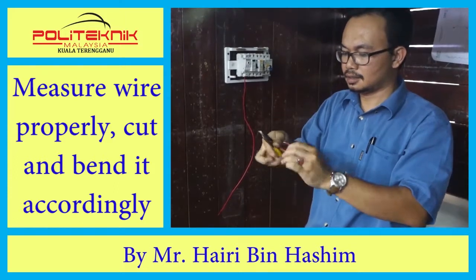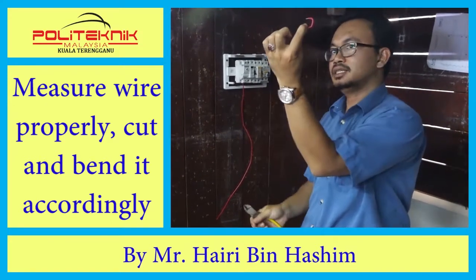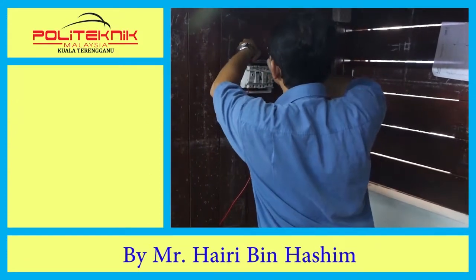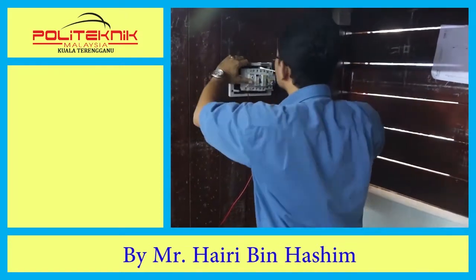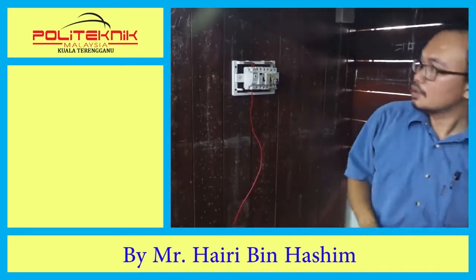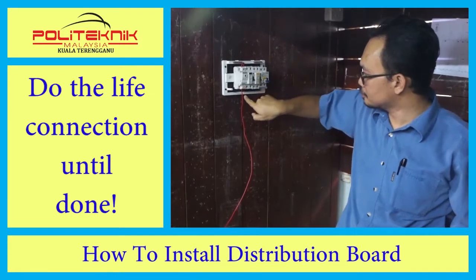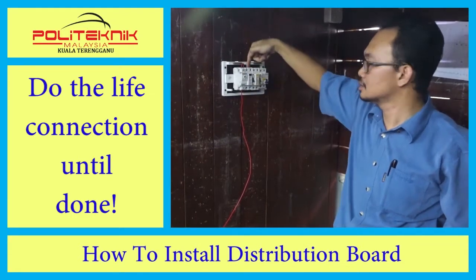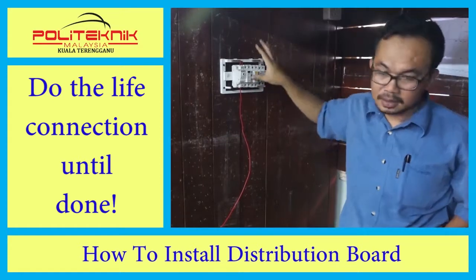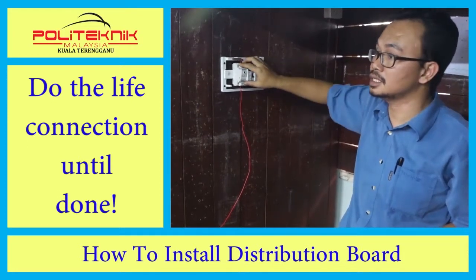After you measure, you bend the wire, you cut it and you strip it, like this, like a C form or U form. What connection do we make? From the main switch, from down goes up, and then into the RCCB from up to down. That's why we cannot install the RCCB or any of these upside down.